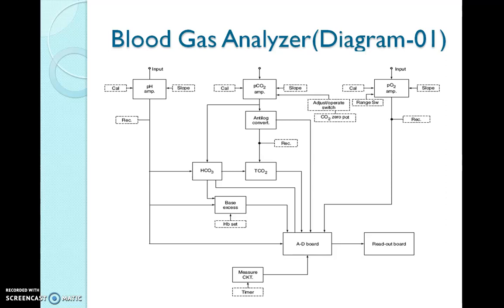A separate module houses and thermostatically controls the 3 electrodes. The analyzer also provides thermostatic control for the humidification of the calibrating gases.